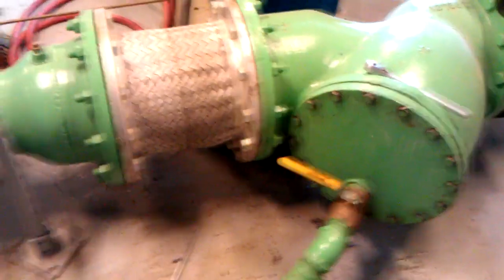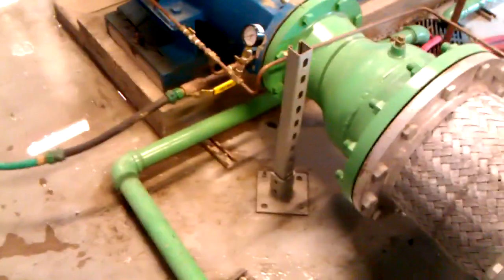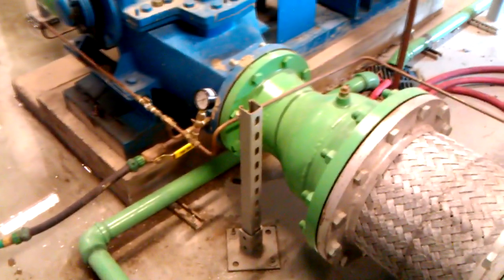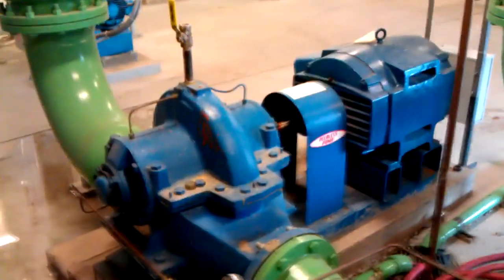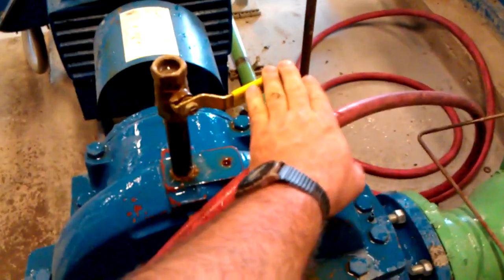Now I need to fill the pump up with water before we even open that up. And if you open that up too early, it'll cause the other pump to freak out. So there'll be a bunch of air. Let the water hose run into the pump, fill that up, so as to get all the air out of the top. Okay, all the air was just purged out of here, as you can see. That's just water from the hose. I will connect this when I first start the pump so it can bleed out.